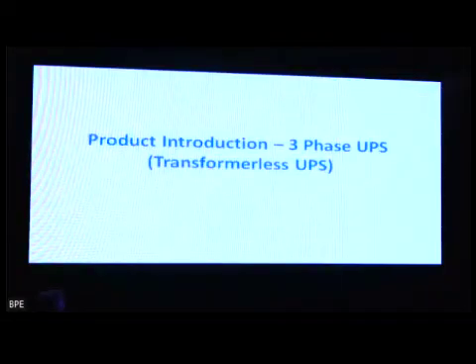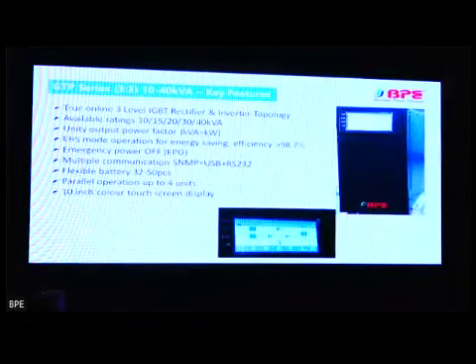Okay, then we will start the three-phase UPSs. First of all, transformer-less UPSs. So starting from GTP series, from 10 to 40 kVA, it's true online 3-level IGBT inverter topology. Battery flexibility is there from 32 to 50 numbers, and this is the unity output power factor product. So kVA is equal to kilowatt, and this has got 10-inch color touch screen display also, and we can parallel up to 4 numbers.